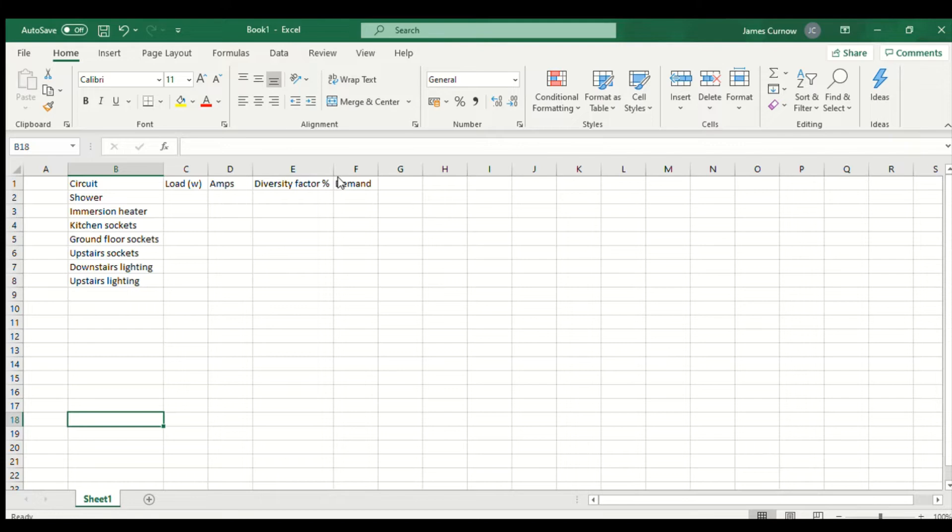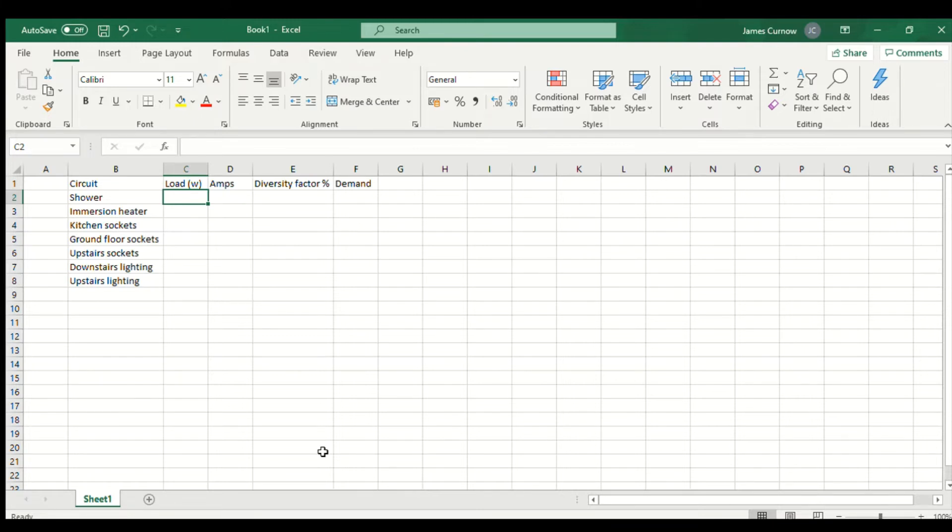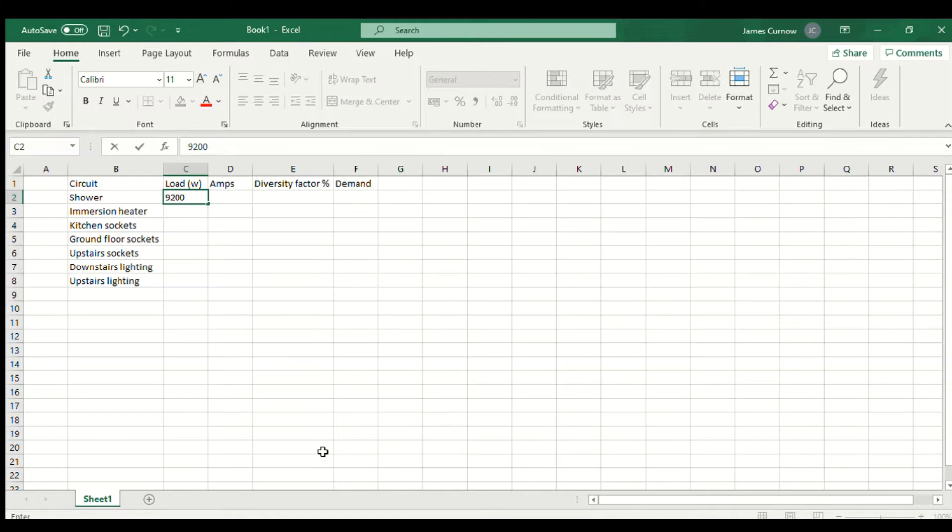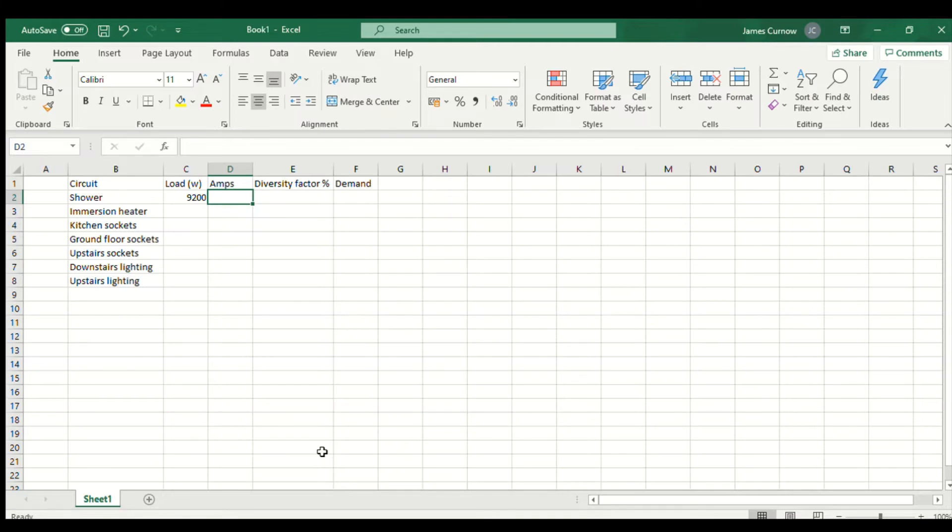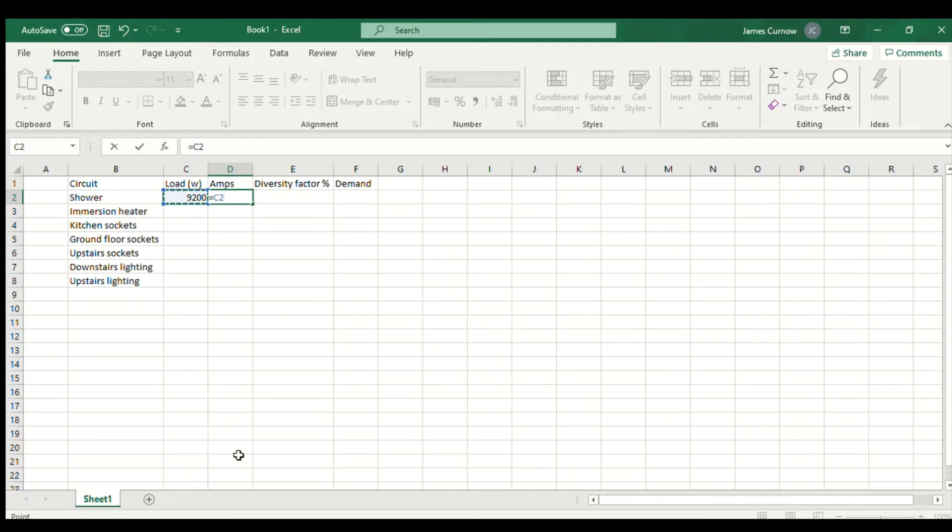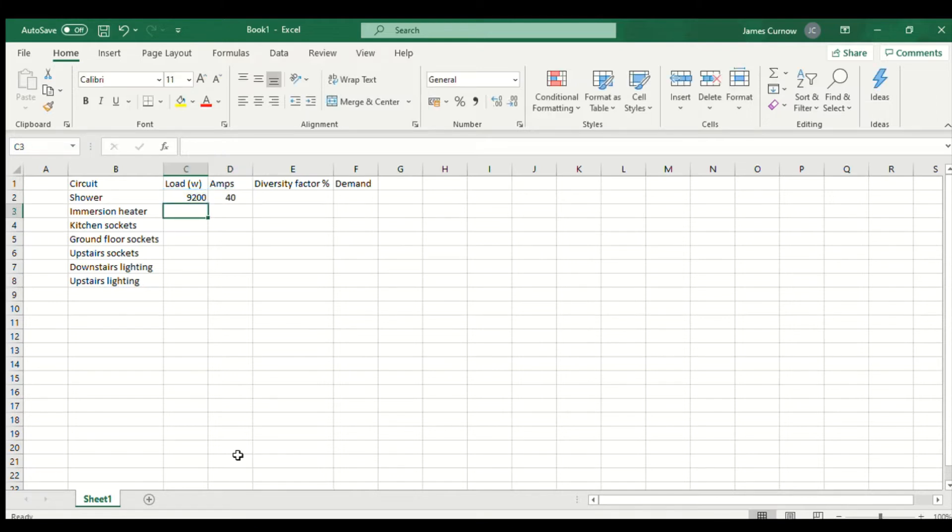For the shower I'm going to assume it's a 9.2 kilowatt shower so we're going to put in 9200 and then calculate the design current simply by pressing equals, clicking on that cell and then forward slash for divide and then 230 volts. With circuits where I know the wattage, I'll always calculate the exact design current.